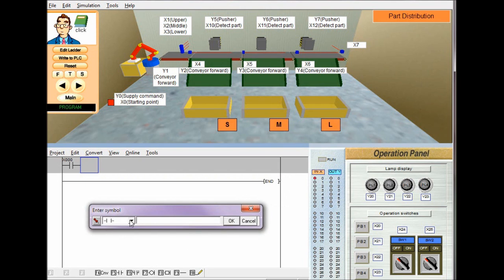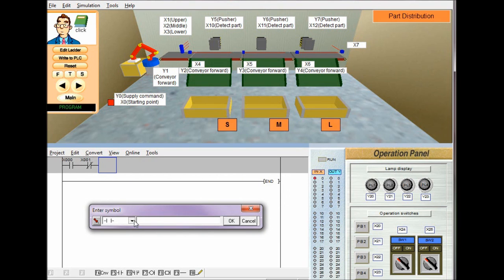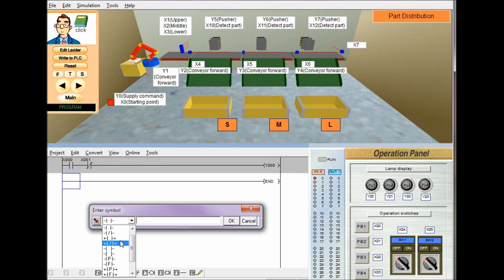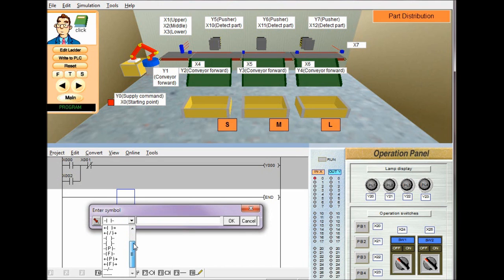We are placing a closed contact named X1 and pressing OK. Outputs are denoted by the letter Y and symbol by closing brackets. So Y0 is an output. The first rung is composed of two input signals and one output — X0 is an open contact, X1 is a closed contact, and Y0 is the output. For branching, two special symbols are used. This symbol creates a branch with a nearby contact in parallel — for example, naming it X2 makes X2 parallel with X0.